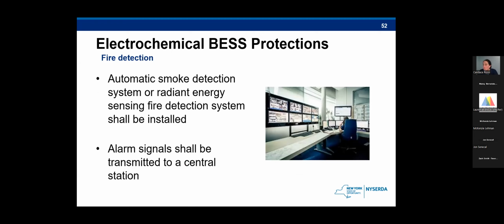So when systems are inside a controlled room or enclosure, the smoke alarm is generally the easiest way to sense a fire. Some installations use technology that is constantly checking the air for any type of abnormal component. You also have the IR radiant systems that check for heat. If there's a temperature rise, it will send a signal to the alarm panel that will notify the fire department that there's a problem. So you have these central stations that are used to monitor fire alarms and make notifications to the fire department that a location is sending a signal from a smoke detector or a radiant heat detector.